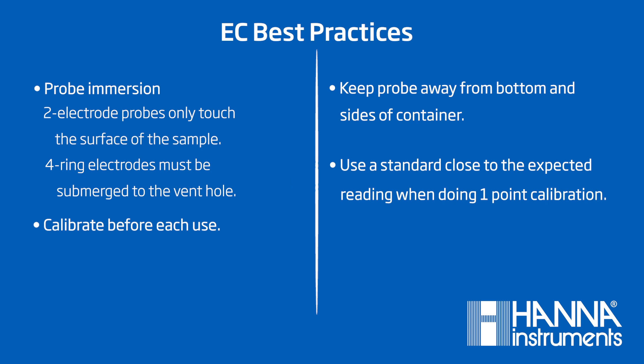Here are a few best practices when using your EC probes. Probe immersion is important. With a two-electrode probe, you only need the probe to be touching the solution. Four-ring probes need the vent holes on the side of the probe to be submerged for accurate measurements.